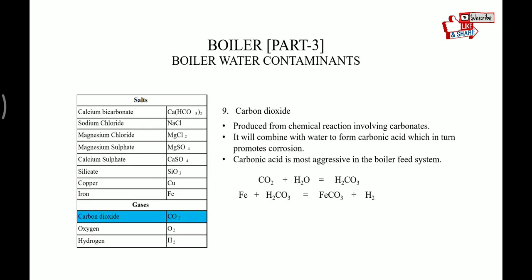Carbon dioxide is produced from chemical reactions involving carbonates. When carbonates decompose, they release CO2, which will combine with water to form carbonic acid, which in turn promotes corrosion. Carbonic acid is the most aggressive agent in a boiler water system that leads to corrosion.